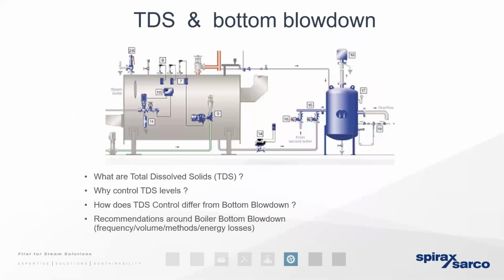So we also discussed blowdown in, I think it was our very first presentation. So both TDS, which stands for total dissolved solids, and the bottom blowdown, well, it needs to be performed because it helps us to maintain the boiler water chemistry. And I think the analogy that I often use is if we've got a cup of tea and we add a spoon of sugar and then a spoon of sand into that cup, well, the sand, that's going to fall to the bottom of the cup.